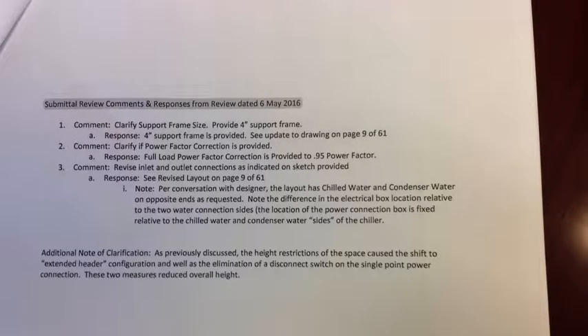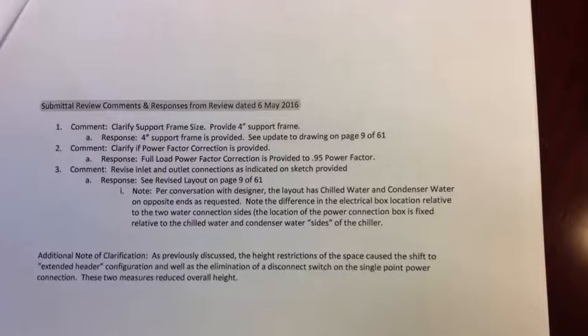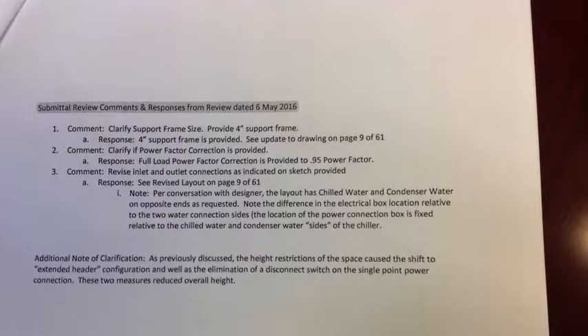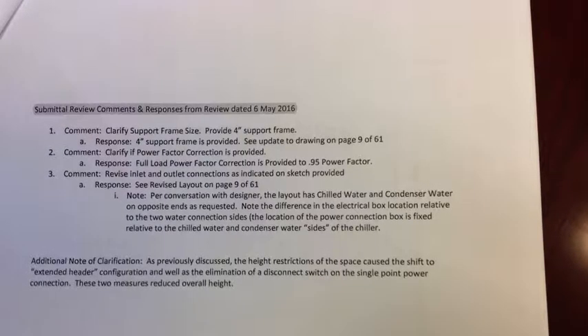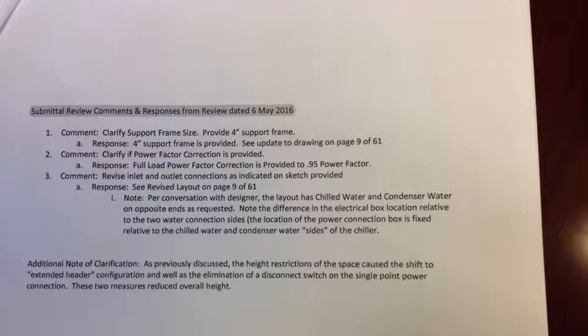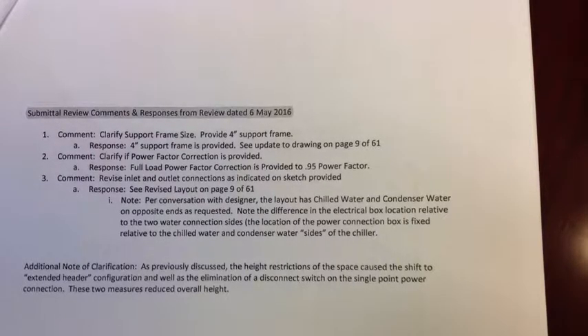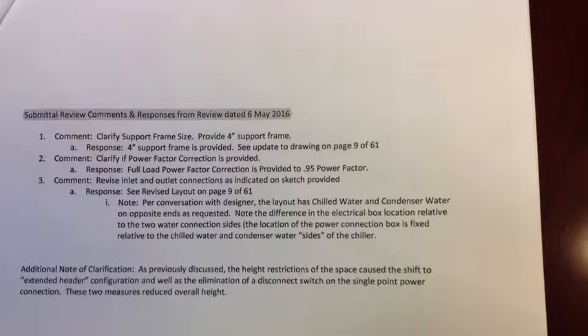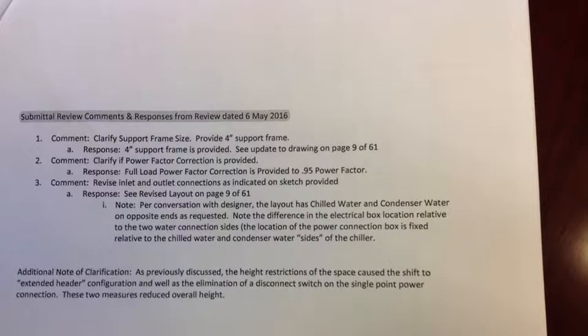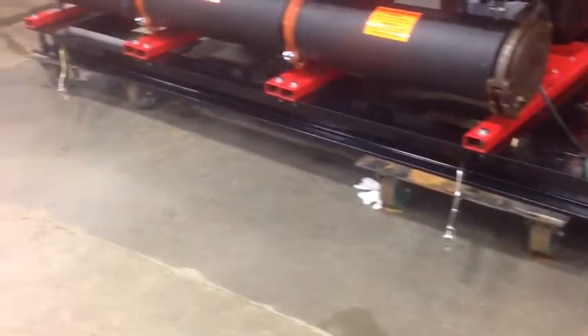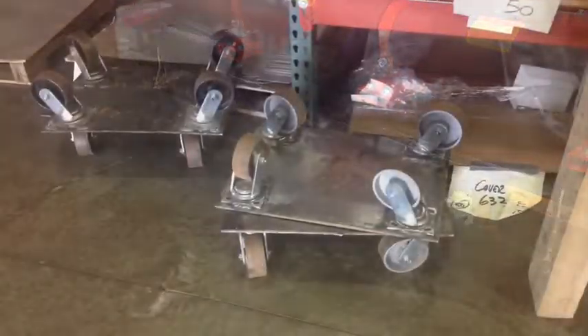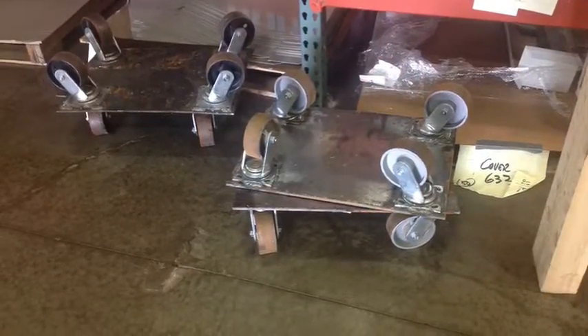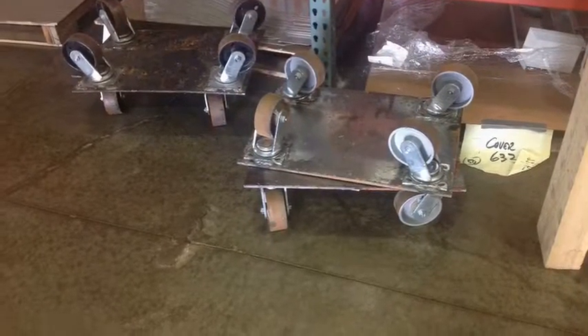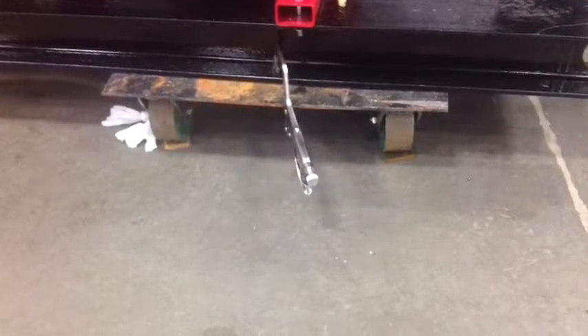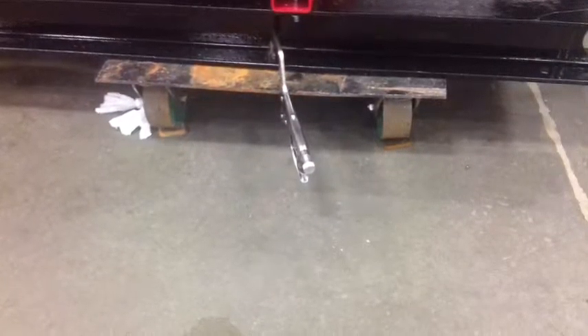Again, we will show a measurement of the 4-inch support frame, talk about the power factor correction capacitors, and we will show pictures of the layout drawing from the submittal, as well as give you a 360-degree view of the chiller itself. This is a picture of the wheel sets that we use to move the chiller around the factory. This is a possible recommendation for you to use during the rigging of the unit at the job site.